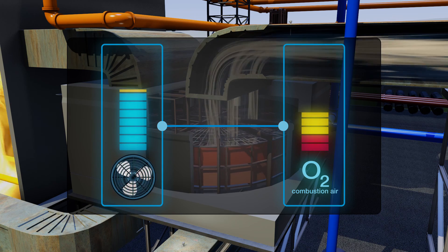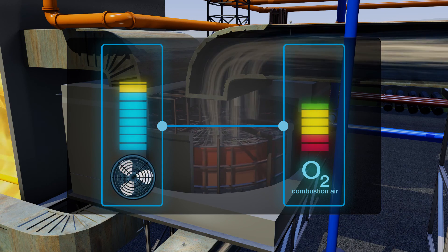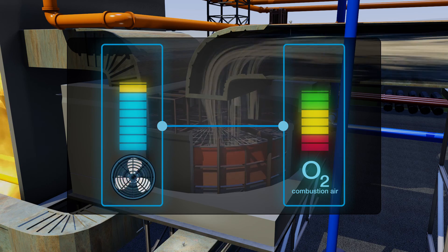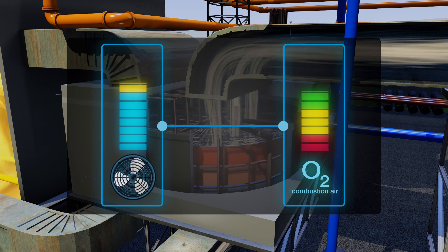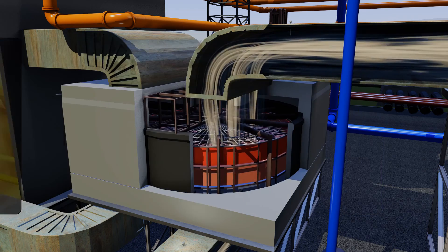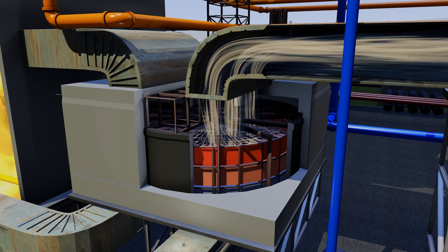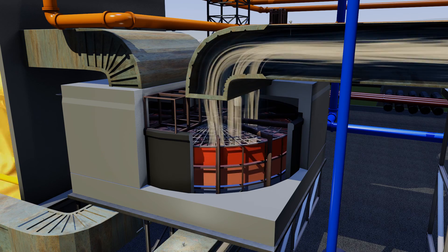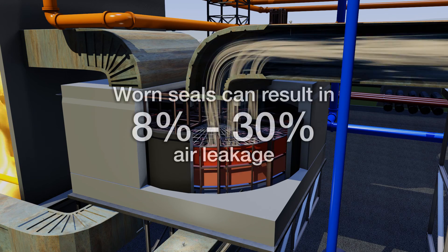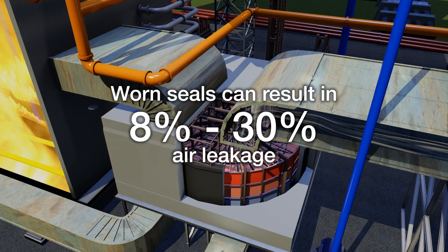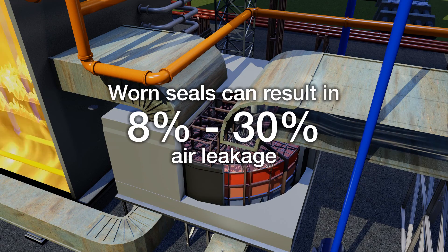Compensating for this lost air means the fan has to work harder, increasing its demand for power. Depending on the design of the rotary heater and the pressure differential between the flue gas and combustion air streams, leakage rates can vary between 8 and 30%.